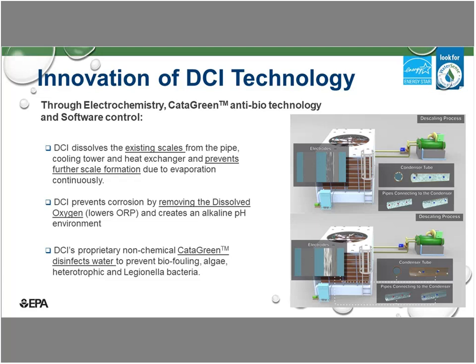So for DCI, we actually consume the dissolved oxygen, so we lower the ORP. The reason we are able to consume the oxygen is because you use the oxygen for formation of your bicarbonates or carbonates, and also to generate the OH minus to regulate the pH. So by reducing the oxygen, you definitely will help with reducing corrosion, and by maintaining a good level of pH.